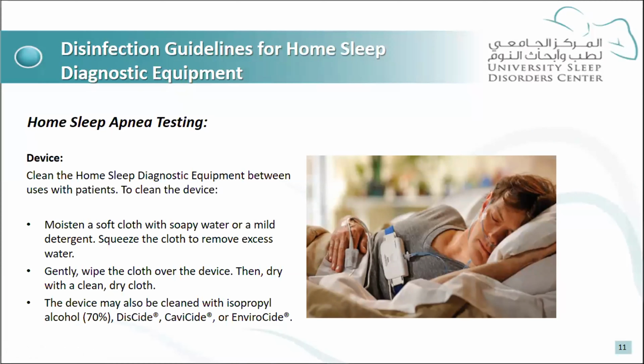So first, I will start with the device itself, and how to disinfect it. In general, to disinfect the device, you need to get a soft cloth. You need to put it in mild detergent and squeeze it to remove the excess solution from it. Then gently wipe the device, and you can only swab this part of the device, okay? So you can swab it. You need to make sure that it is dry before using it for the next patient.